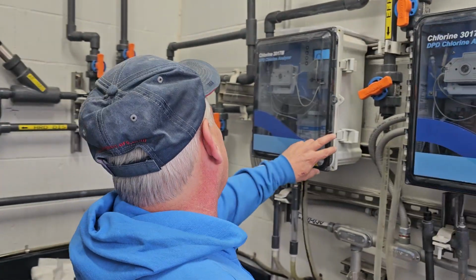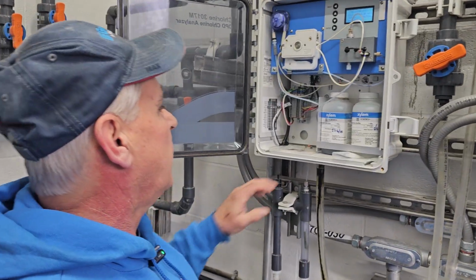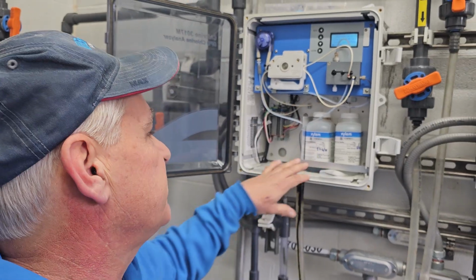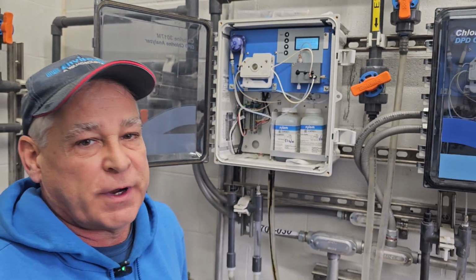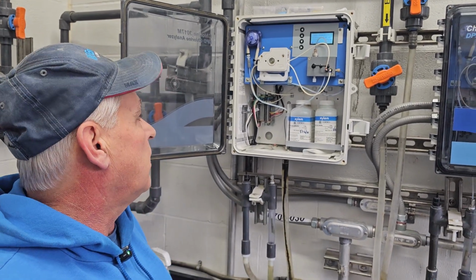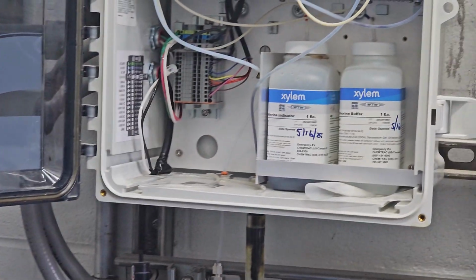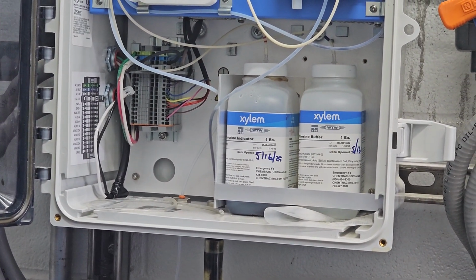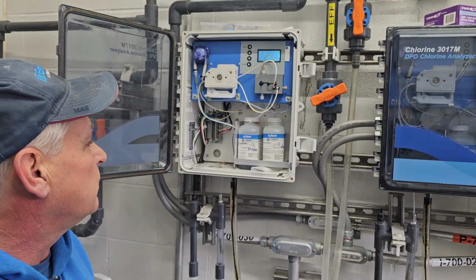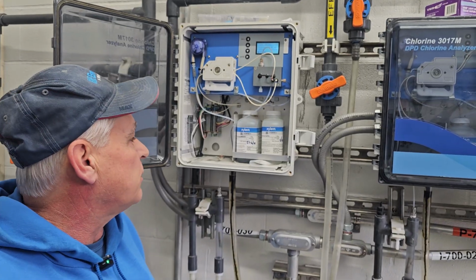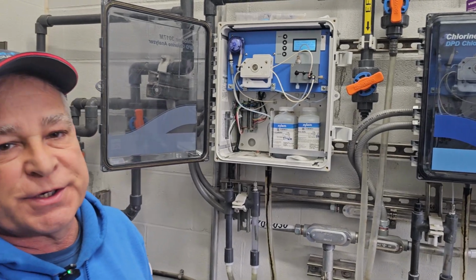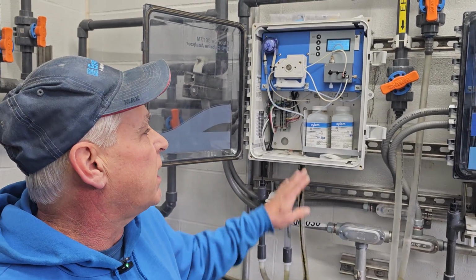All right, so we'll start over here with the 3017 chlorine analyzers. What we're going to want to do is make sure that these reagents are changed and fresh every month. It sounds like this equipment's not going to be running except during storm, high flows. So I guess you could also play that by ear and put fresh reagents in when you know we're going to be running the analyzer.